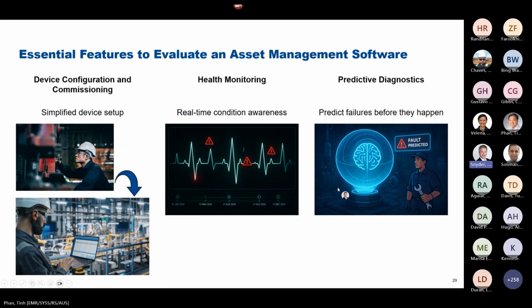Beyond just having an online connection to monitor health and do troubleshooting so you can plan corrective actions, a next step is predictive diagnostics. There are advanced applications for certain types of devices. A lot of people start with control valves, since mechanical moving parts wear out faster than a sensor or probe on a transmitter, so they want diagnostics on those. Many manufacturers offer advanced valve diagnostics built into these asset management systems or as an option. There are also other advanced applications around interlock verification.